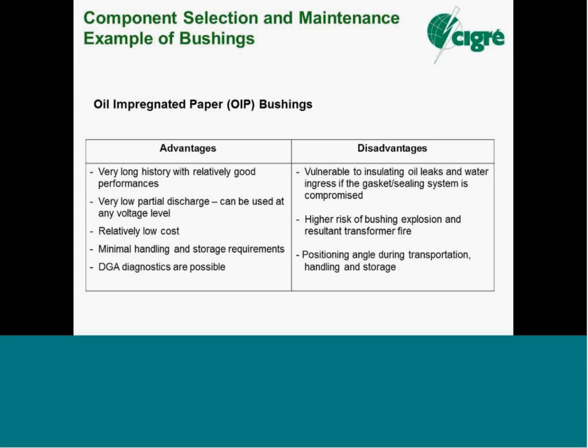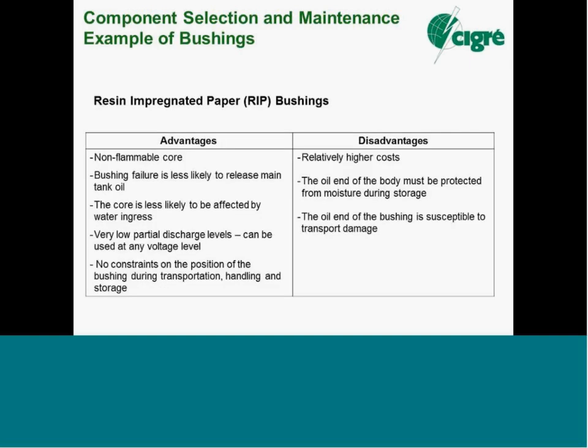So it's been recognised that the resin-impregnated paper bushing has a distinct advantage over the OIP bushing. Something to be considered when there's a critical asset or nearby assets at risk for a major oil fire. There's the advantages and disadvantages of the resin-impregnated paper bushing coming next, and its advantage, a non-flammable core, less likely to be affected by water ingress when it's mounted in the transformer. As you see in the disadvantages to the right, the oil end of the bushing must be protected from moisture during storage. So less affected by water ingress mounted in situ in the transformer. They're quite vulnerable to moisture, not protected on its exposed oil ends in storage.